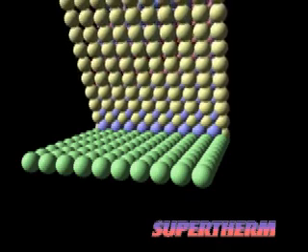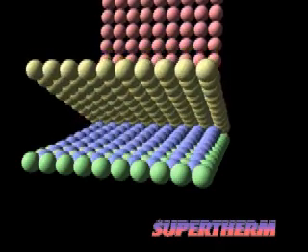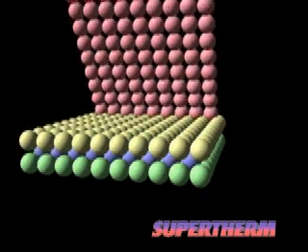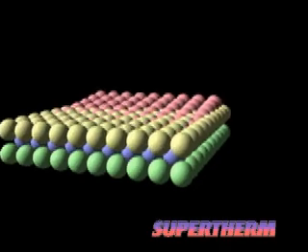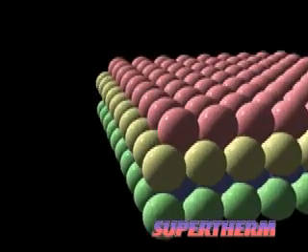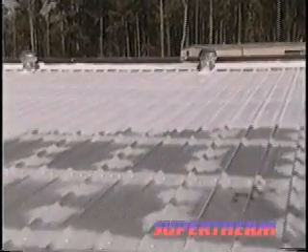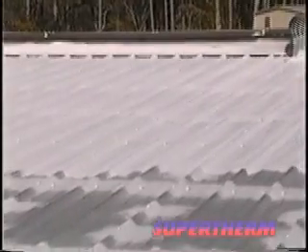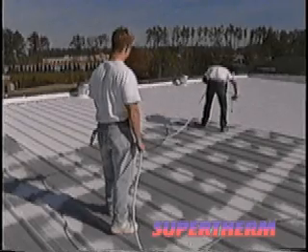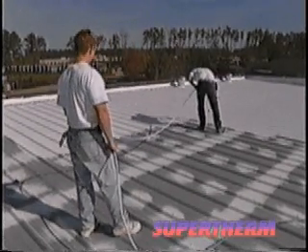One ceramic is actually non-conductive. A second ceramic repels better than 92% of shortwave radiant heat, and a third ceramic repels better than 99% of long-wave radiant heat. There's another ceramic that repels infrared. These ceramics in combination have allowed this coating to achieve an R19 insulation value as tested by independent laboratories, or the equivalent of 6 to 8 inches of fiberglass batt insulation with merely a 7 dry mil thickness coating.